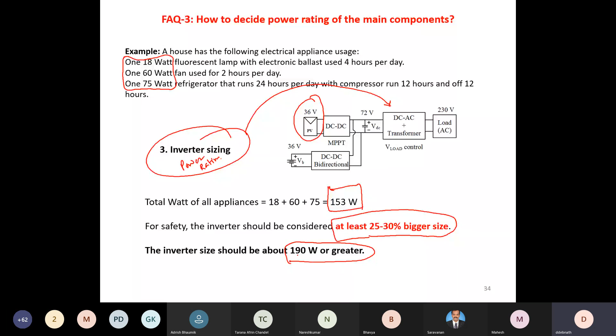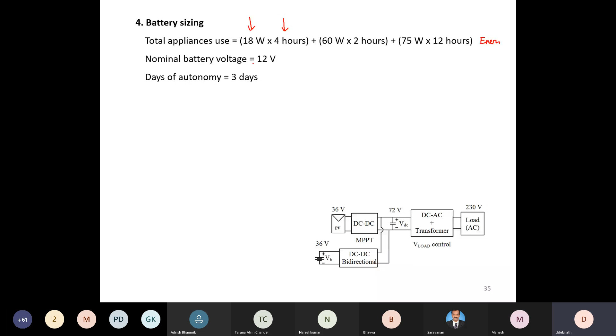Next question: how do we do battery sizing? This is very important. For each day, we know our energy demand, based on the loads we took and for how long they need to be supplied. For this, you also take a battery voltage of 12 and select the days of autonomy. For example, during monsoon time your solar isn't available, so how many days should your battery supply power continuously without solar? That's your days of autonomy — let's say it is 3 days.